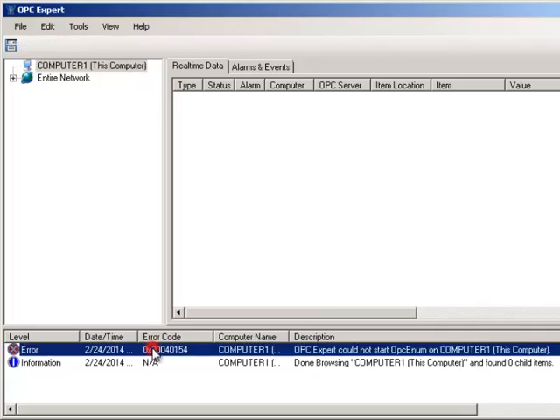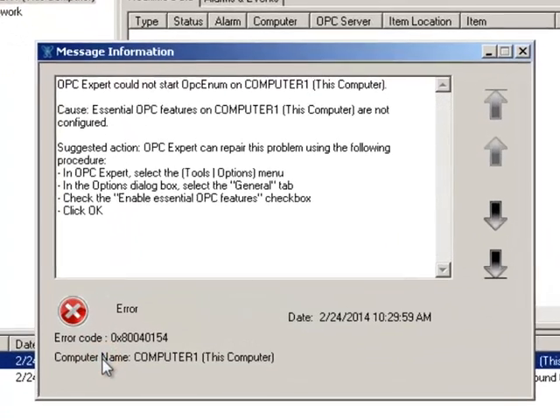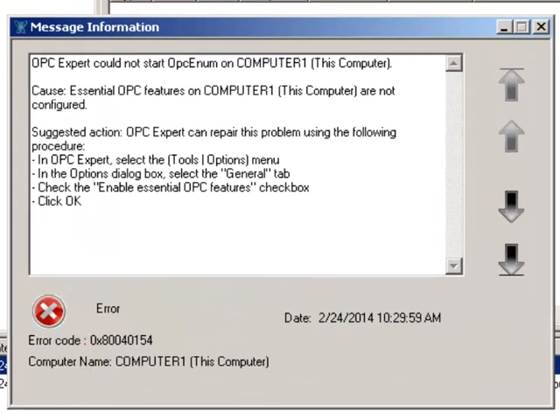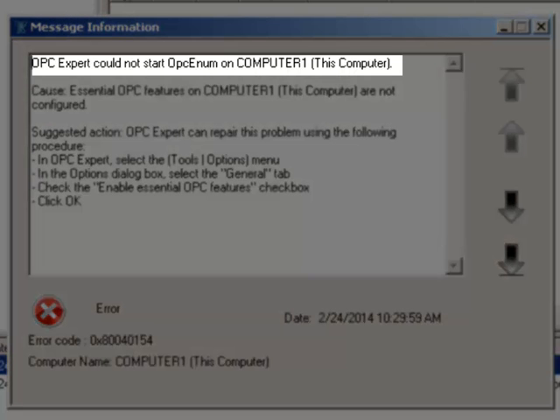When we double click the error, we can see a verbose description of our issue. Like most OPC applications, OPC Expert uses OPC Enum to find available OPC servers. But, OPC Expert could not start OPC Enum.